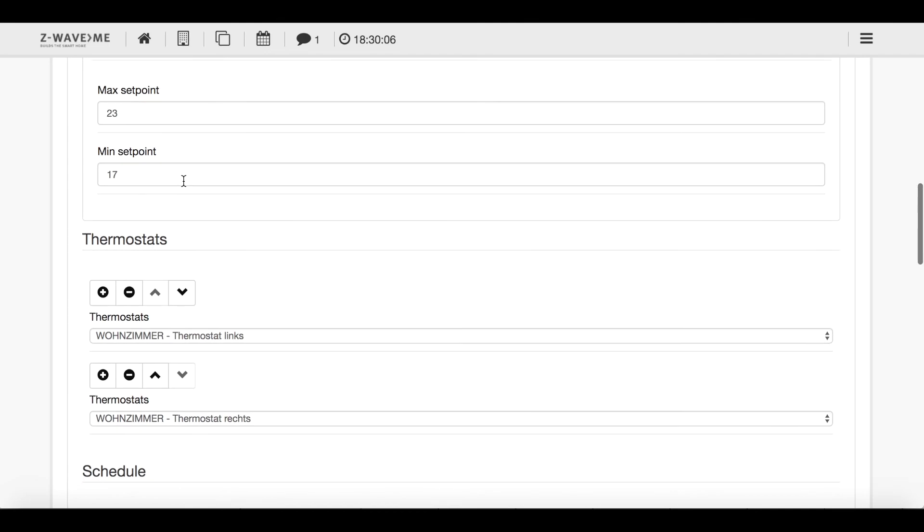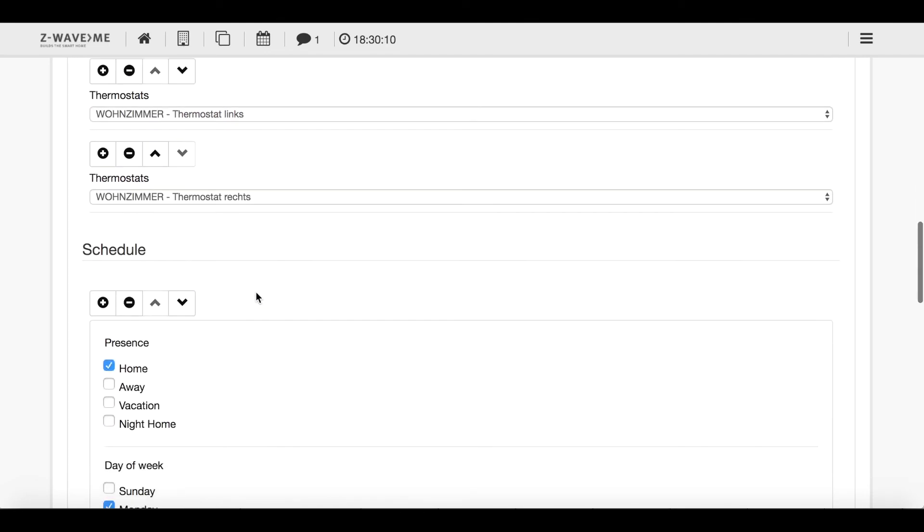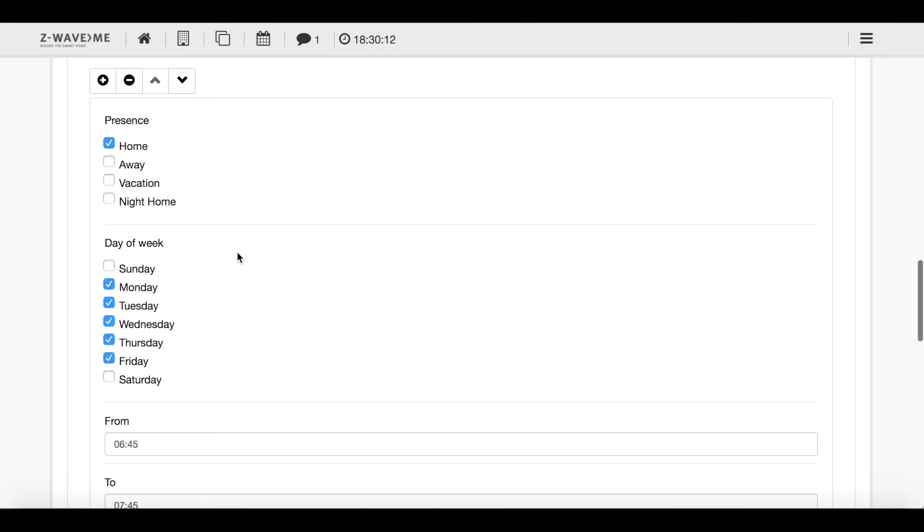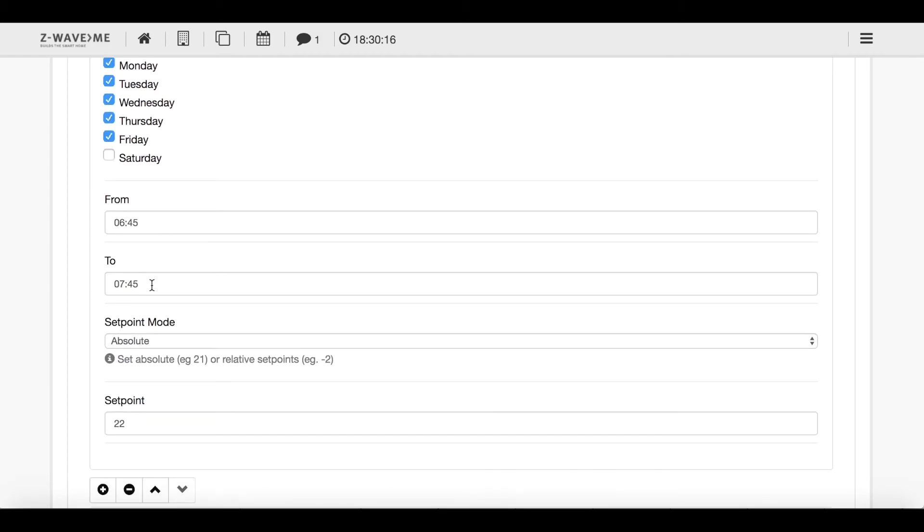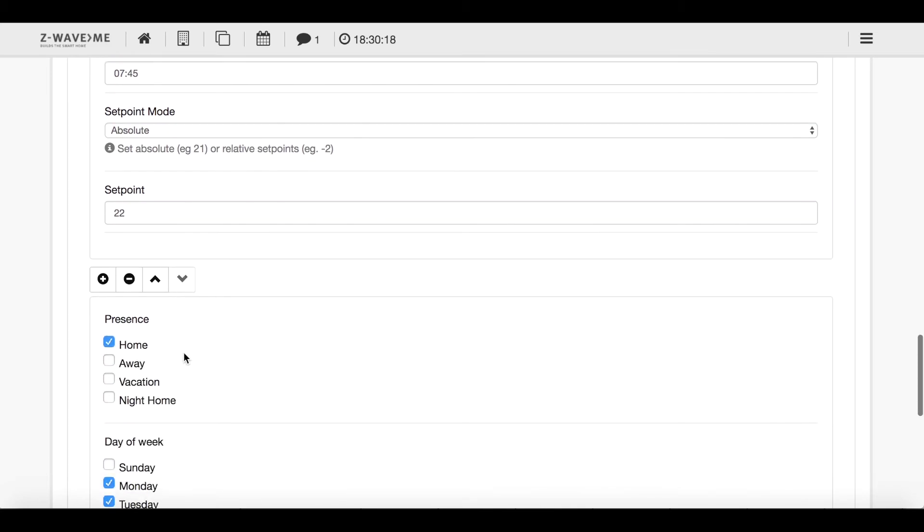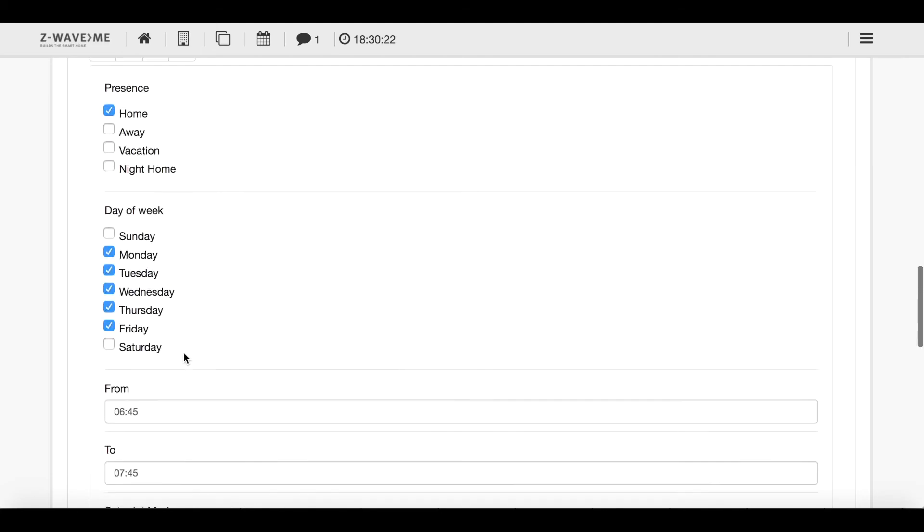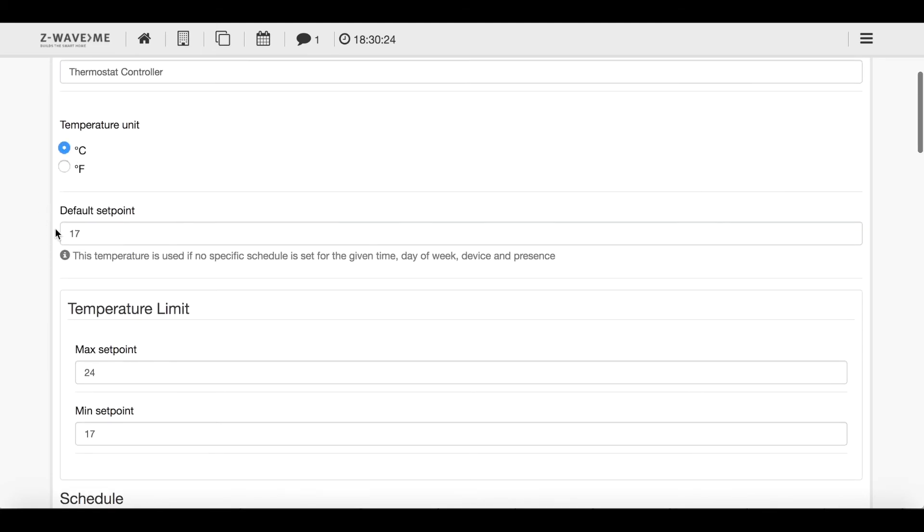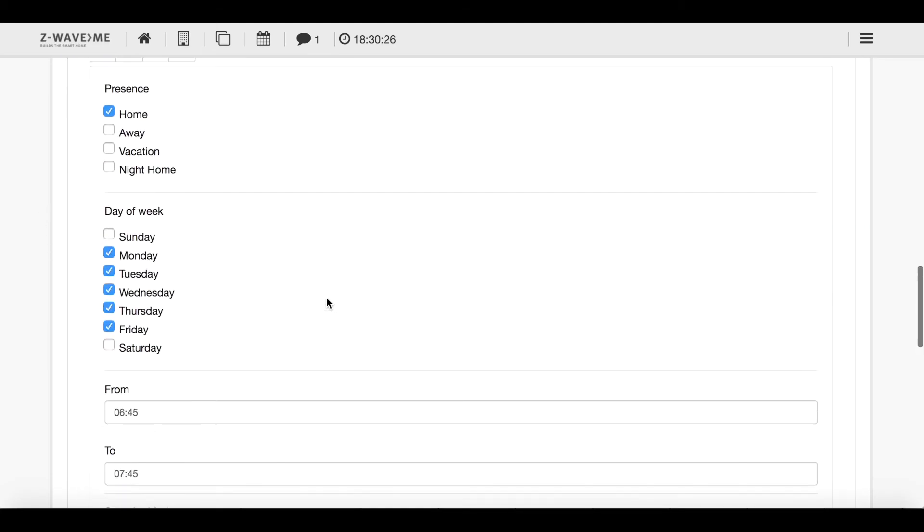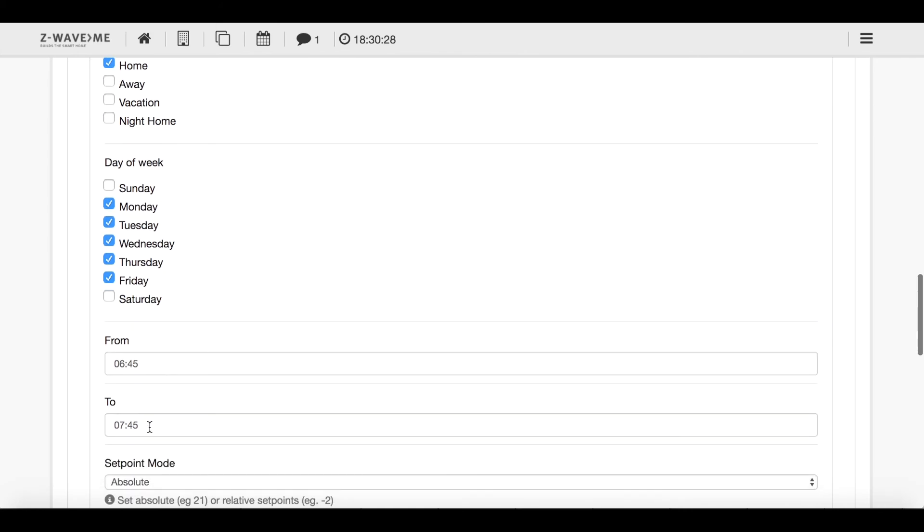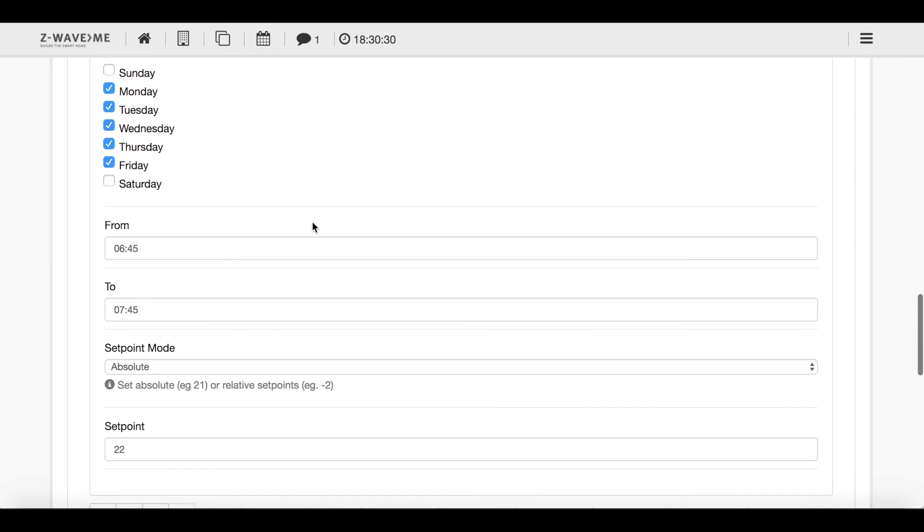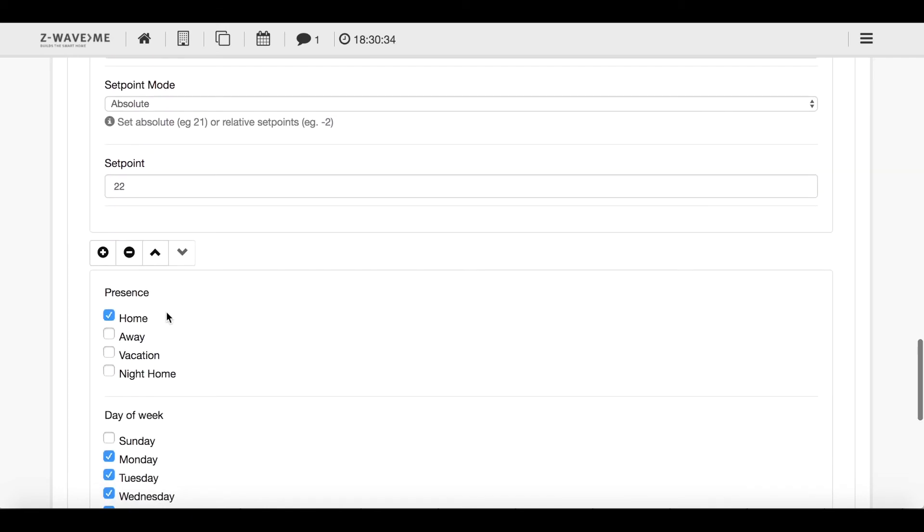I have maximum set point, a minimum set point. I have the two thermostats which are in that zone. And when I'm at home, when the icon is set to home in the morning from 6:45 to 7:45 it will heat to 22 degrees. After that it will go back to 17 degrees. So it will go back to this default set point because there is no schedule for the time after 7:45. So that's very neat that I don't have to set another time period for the time I'm not at home.